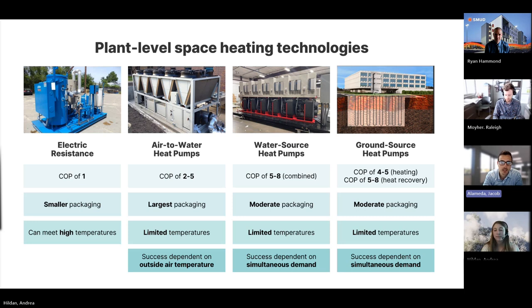out of it. The benefit of that equipment type is that they have small footprints. They don't need to be outdoors, and they can give you really similar heating water temperatures that you would expect from a traditional gas boiler. The downside is that it is a third as efficient as a heat pump, and using it as the main source of your heating for your building can lead to large electricity demand charges and operational costs down the road.